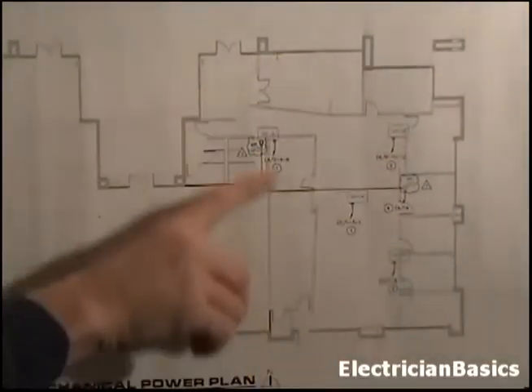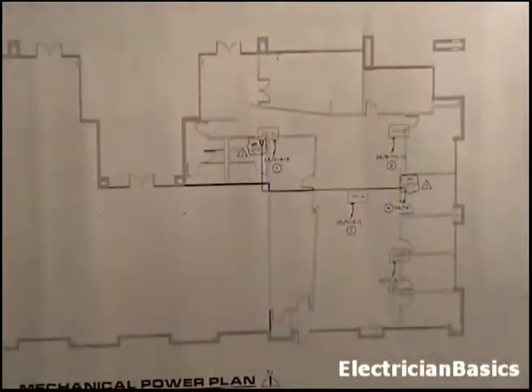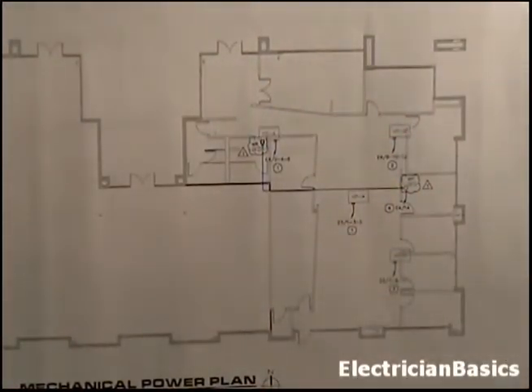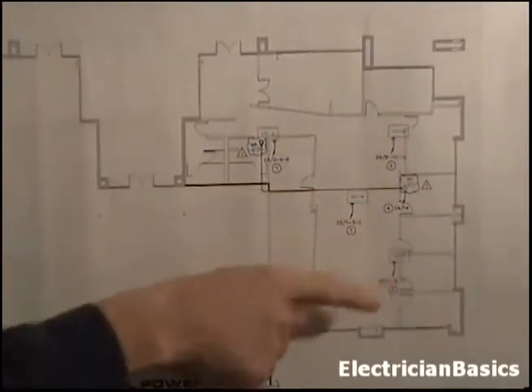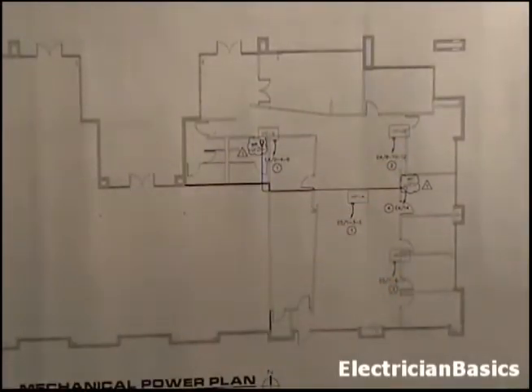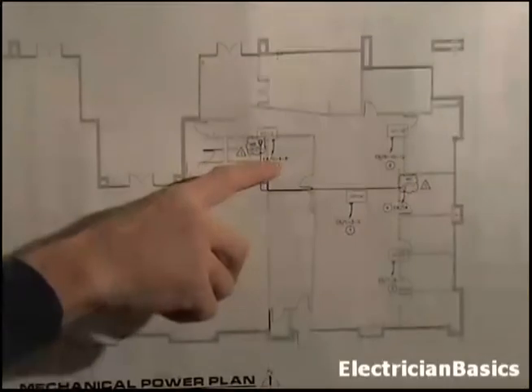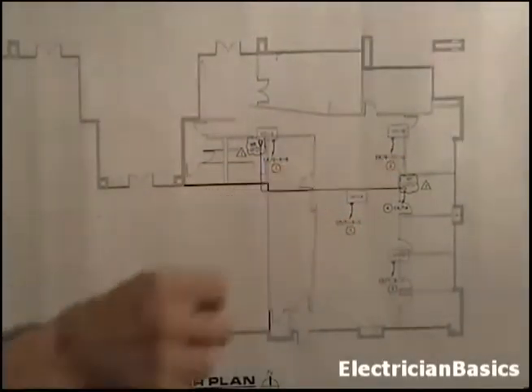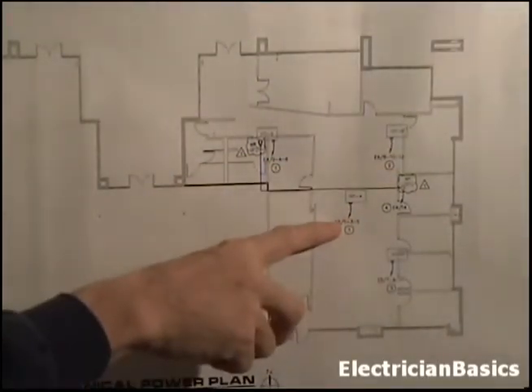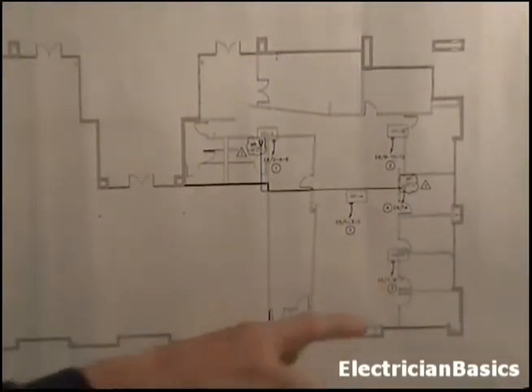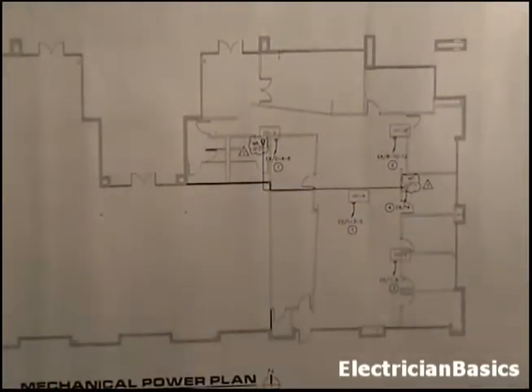This is our section, our build out part of the building, and we have 4 heat pumps if you remember. Here they are. And you remember the types, they had A, B, and a C type, and here's an A and a B, another A, and here's the C. We have here panel E4, circuits 2, 4, 6, E4, 8, 10, 12, and these next two are on panel E5, 1, 3, 5, and E5, 7, 9, 11. So they've split the heat pumps up onto 2 different panels, so you just have to be aware of that and just don't make an assumption that they all go to the same panel.